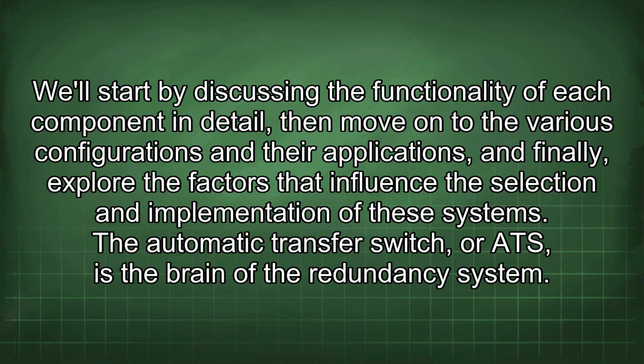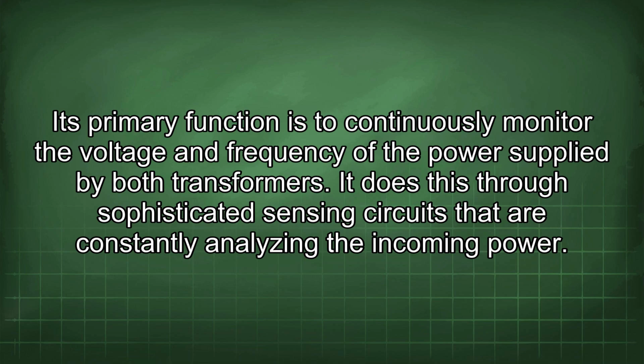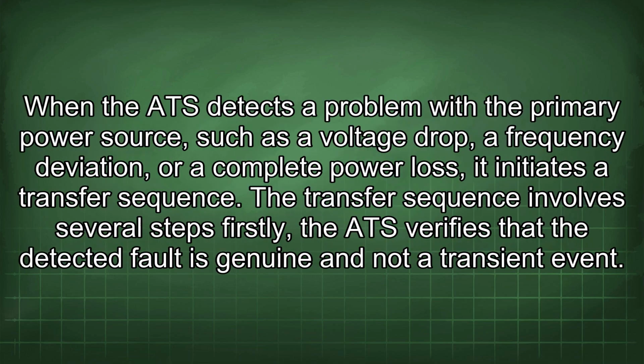The automatic transfer switch, or ATS, is the brain of the redundancy system. Its primary function is to continuously monitor the voltage and frequency of the power supplied by both transformers. It does this through sophisticated sensing circuits that are constantly analyzing the incoming power. When the ATS detects a problem with a primary power source, such as a voltage drop, a frequency deviation, or a complete power loss, it initiates a transfer sequence.